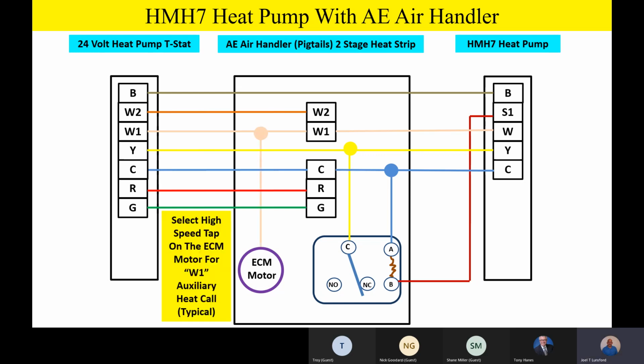Notice on the ECM motor also what we're going to do before we hook up any of the normally closed or normally open switch functions on the relay: we want to make sure that we grab the high-speed tap on the ECM motor and hook it onto the W1, or first stage auxiliary heat, terminal. The reason we do that is anytime we go into defrost mode or call for auxiliary heat, we're going to drive that indoor fan motor to speed tap number 5 to make sure we have plenty of airflow. We don't want to overheat the heat strip when we go to auxiliary heat, and we just want to make sure that we have adequate airflow. So typically, the most common spot to put that number 5 speed tap on that ECM motor is on our W1, or auxiliary heat, terminal.